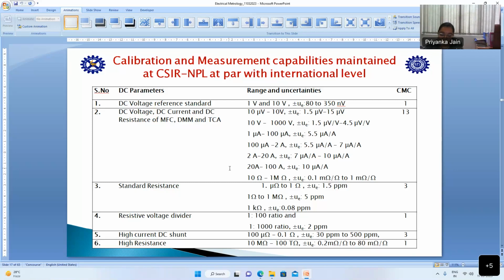One is the resistive voltage divider. It is capable of delivering ratios of 1:100 and 1:1000. The uncertainty is around 2 ppm. Next are high current DC shunts. We have shunts of 100 micro ohm to 0.1 ohm, capable of taking current from 100 amps to 600 amps. The uncertainty for that is 30 ppm to 500 ppm. The last one is high resistance. Using teraohm bridges and electrometers, we establish these uncertainties from 10 megaohm to 100 teraohm. The uncertainty is in the range of 0.2 milliohm per ohm to 80 milliohm per ohm. So this is some of the basic CMC work.